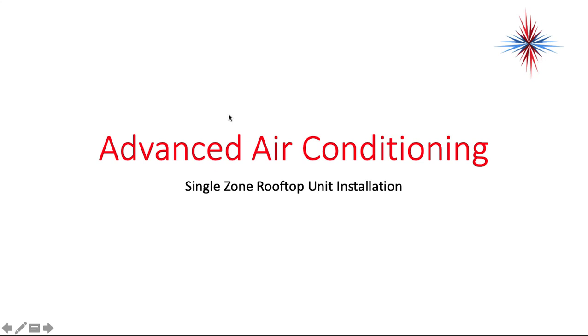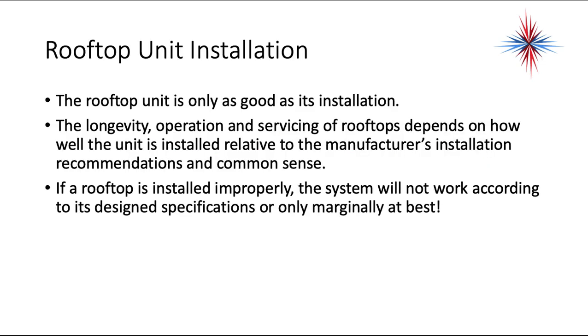We need to talk a little bit about rooftop units, otherwise known as package unit installation. We've been talking a lot about split systems and the proper ways to install and handle split systems, but let's talk about the rooftops. A rooftop unit is only as good as its installation.